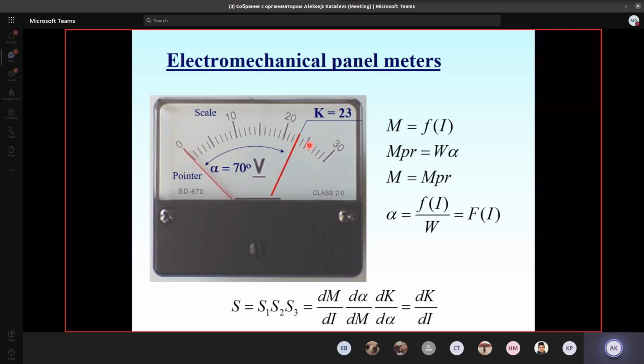The principle of this kind of operation is usually some magnetic or electric force that provides a turning, rotational momentum to the index. The frame of the index has a spring or torsion spring attached, which provides a return moment. The moment that forces the index to turn usually depends on the current or voltage applied to the device, while the moment of the returning force from the spring is proportional to the deflection angle.